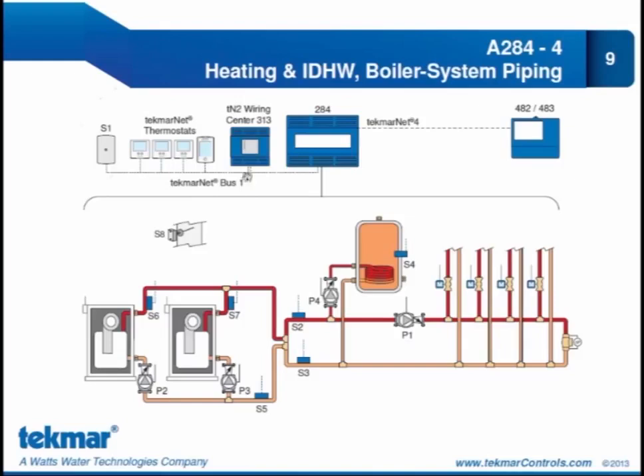The outdoor temperature reset, which is possible because of this outdoor sensor connected to the 284, plus the indoor temperature feedback, saves energy by operating the boiler plant using the lowest possible temperatures. And lower water temperatures are, of course, excellent conditions for the modulating condensing boilers. It allows them to operate at maximum system efficiency. You can also see here there is S8, and this is what we call a vent sensor.